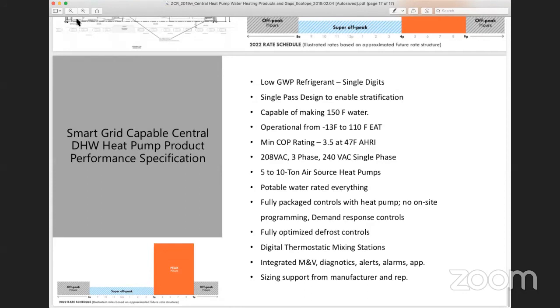Right now, we're setting up all of our heat pump systems with custom DDC controls with alarms and automatic backup systems. This is really the only way to stay sane when we've got issues. I mean, we're still early life on some of these heat pump products, and things happen, so we have to stay on top of them. But back to the product: fully optimized defrost controls. We use digital thermostatic mixing stations for all of our hot water loops and plants. And having integrated M&V and diagnostics, alerts, and alarms is really nice.